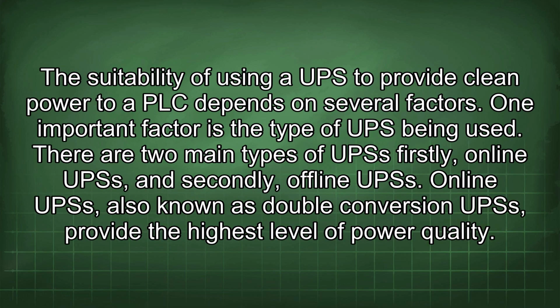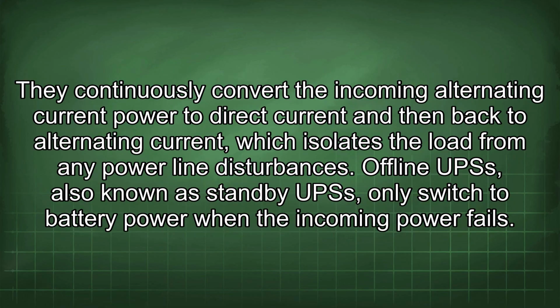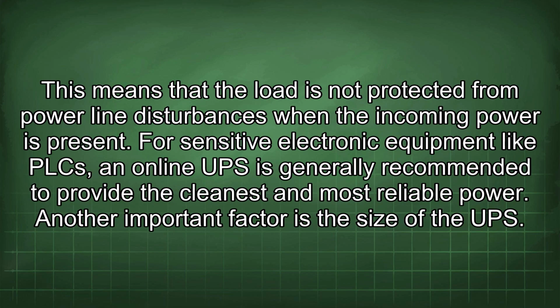The suitability of using a UPS to provide clean power to a PLC depends on several factors. One important factor is the type of UPS being used. There are two main types of UPS: firstly, online UPS, and secondly, offline UPS. Online UPS, also known as double conversion UPS, provide the highest level of power quality. They continuously convert the incoming alternating current power to direct current and then back to alternating current, which isolates the load from any power line disturbances. Offline UPS, also known as standby UPS, only switch to battery power when the incoming power fails. This means that the load is not protected from power line disturbances when the incoming power is present.